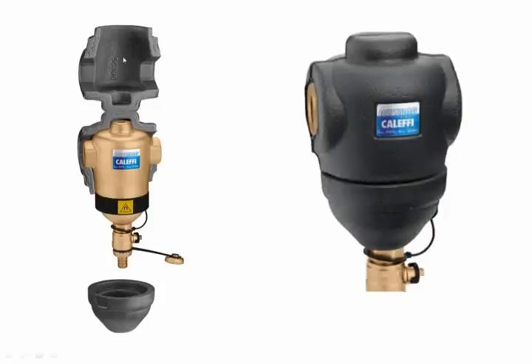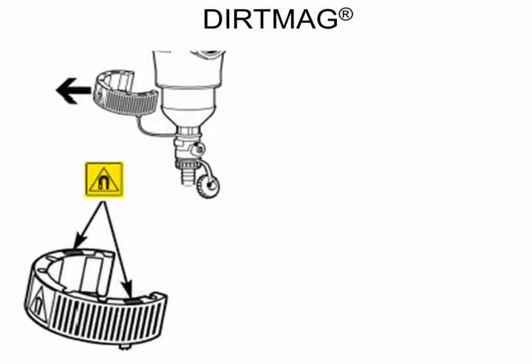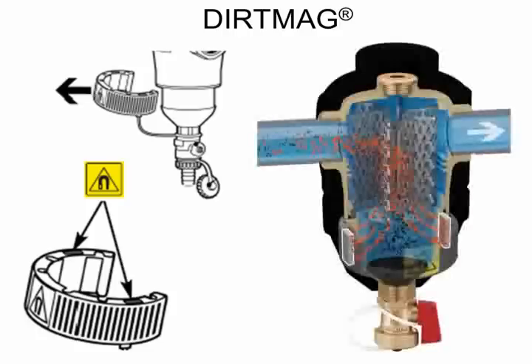So let's jump to dirt separators, then we'll go into hydraulic separation. Here's a dirt separator, and it comes with insulation as an option, and I don't want to talk so much about that, but what I want to point out is this little black ring. What is this black ring? Well, it's a magnetic collar, and that magnetic collar has rare earth magnets, neodymium ferrite magnets, the same kind of magnets that are used in ECM pumps, the high-efficiency pumps that are becoming more and more commonplace. So now we have a line of product where we've taken this magnetic effect and we've placed it on the dirt separators.